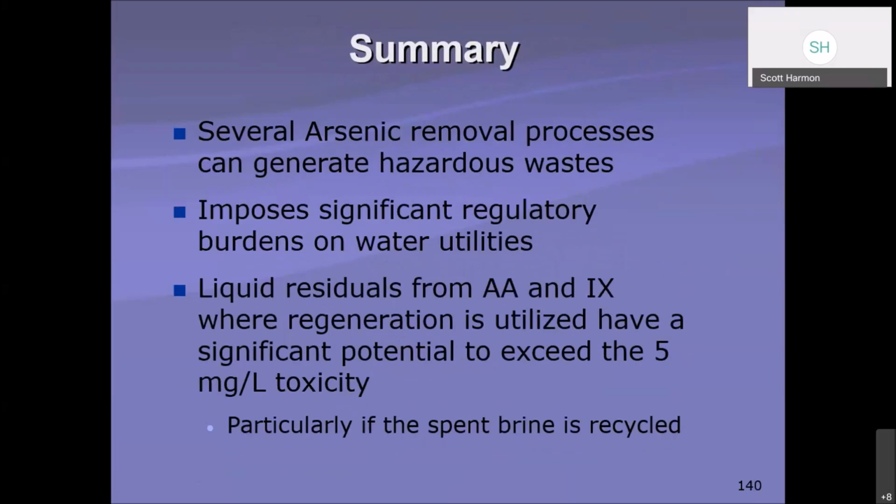So here's a brief summary. Several arsenic removal processes can generate waste. That's a given. It can impose significant regulatory burdens on your utility, and it will. Liquid residuals that are regenerated or utilized have a significant potential to exceed that 5 milligrams per liter toxicity level, particularly if spent brine is recycled. That's just trying to tell you, the more you concentrate a substance, the greater shot you've got of getting it above that 5 milligrams per liter toxicity level.